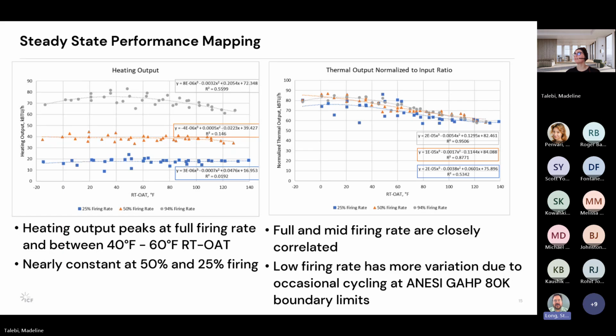Yeah, I would say field testing is finding lots of challenges with realistic COPs, not because of the unit performance, but because of system integration. And there have been some additional issues. We've not seen those as much, but just in general, the GAHP units need to be running flat out all the time, ideally would run when they cycle. They don't tend to work as well. I don't know if we've got a graph of that here, but in essence, they need to run a good 45 minutes until you're really at steady state COP. So if they cycle a lot, you're going to get poor field performance. If you keep them on, base loaded type of thing, you should be getting something pretty good.